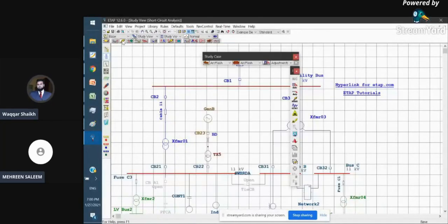In case of short circuit analysis, in the past ETAP was used for short circuit mode as well as arc flash, but in the newer versions arc flash has been separated. So now there is one study case created for IEC 60909 type of study. This short circuit simulation is based on IEC 60909.